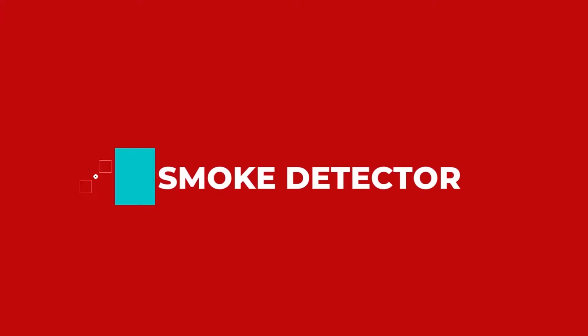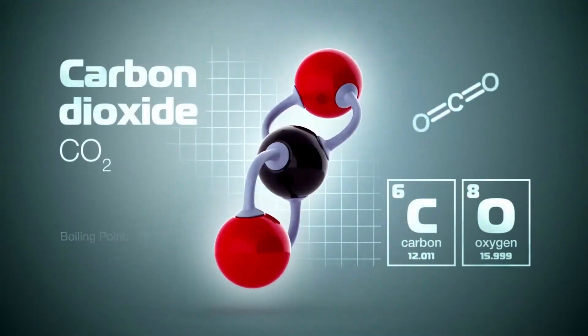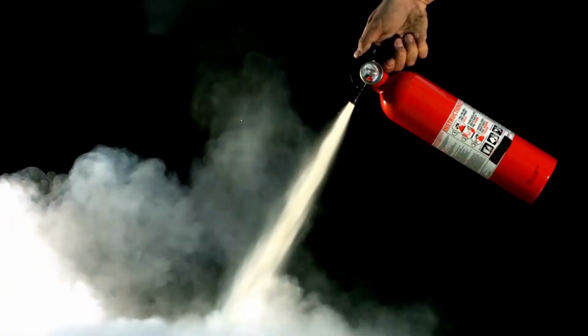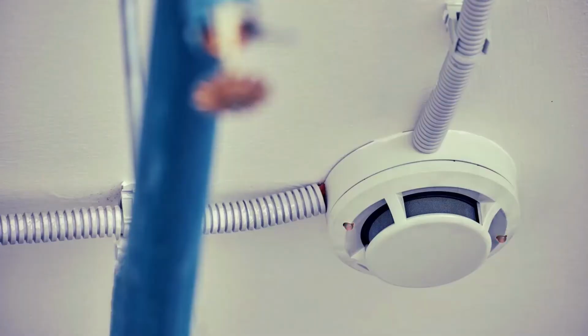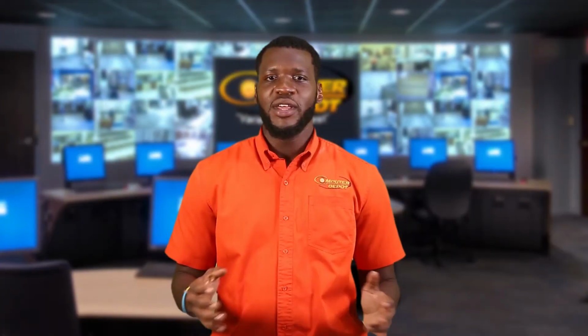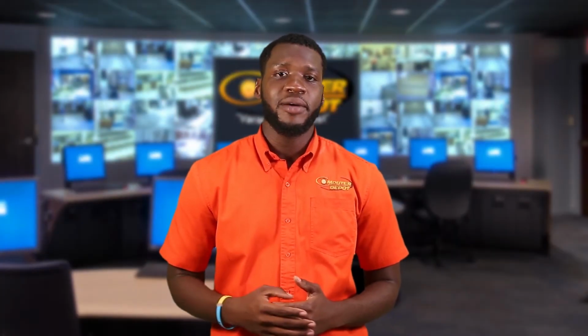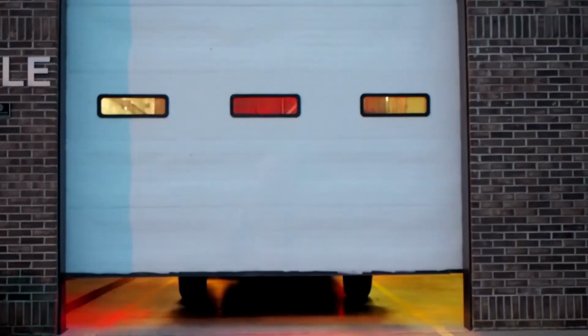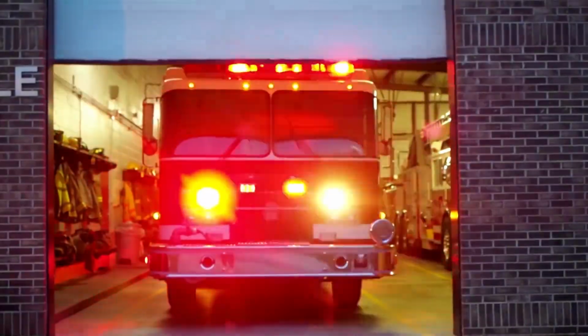Smoke detectors. Smoke detectors are devices that can detect smoke, carbon, and heat, normally as an indicator of fire. Smoke detectors, when connected to the security systems, should be connected to the fire zone, but if there is no fire zone, a regular zone should be programmed to represent this zone. When the fire zone is triggered, special commands and responses will be initiated to mitigate losses to the premises. For example, this trigger will call the fire department directly.